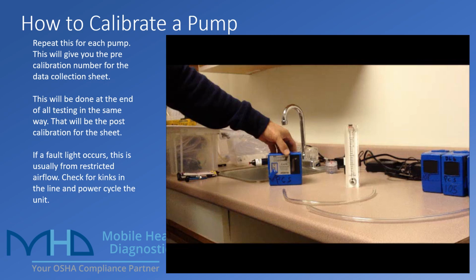The other thing that you might see is a fault light. So if you see a red LED that starts to blink and or the pump has turned off, but the power switch is on, that is usually due to a restricted airflow. You're going to want to make sure that your lines aren't kinked at all, because if there's too high of a restricted airflow, the pump will just automatically shut down. This can be both important for the calibration step as well as when you're just monitoring during test day. As you're going around to check, that's one of the other reasons that we need to check, is if those lines get inadvertently kinked, the pumps will shut down and we're losing testing time, which is why we need to periodically check on those. In order to fix it, all you need to do is fix the kink, turn the pump off, turn the pump back on.